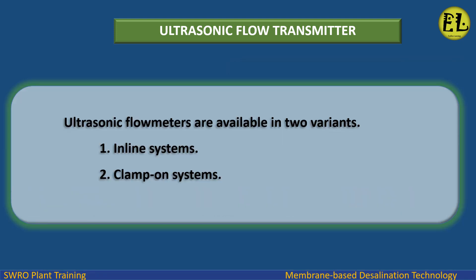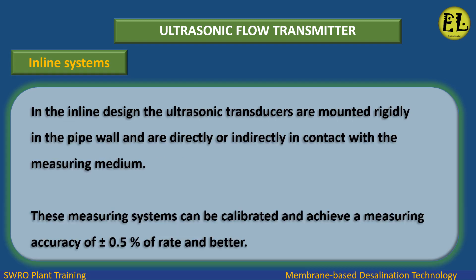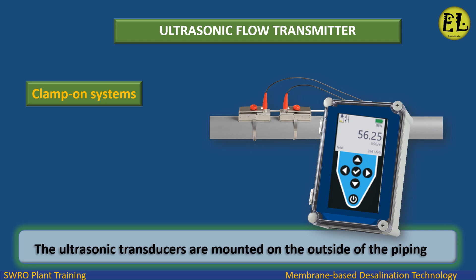Ultrasonic flow meters are available in two variants: inline systems and clamp-on systems. In the inline design, the ultrasonic transducers are mounted rigidly in the pipe wall and are directly or indirectly in contact with the measuring medium. These systems can be calibrated and achieve a measuring accuracy of plus or minus 0.5% of rate or better. In clamp-on systems, the ultrasonic transducers are mounted on the outside of the piping.